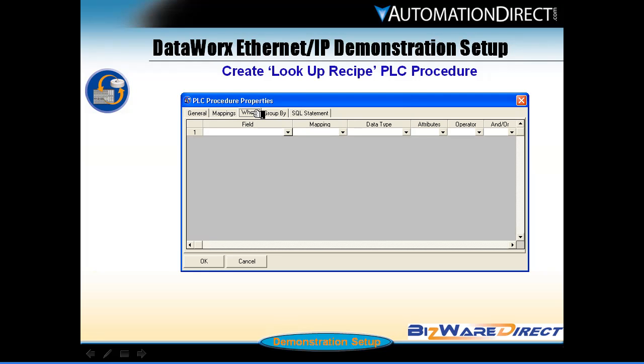In the Where tab, we specify which vMemory location in the PLC we want to use as the filter for DataWorx to look up a particular recipe. Later, we will put the recipe code in V2023. We want DataWorx to find the record in the table that has a code field equal to the contents in V2023.